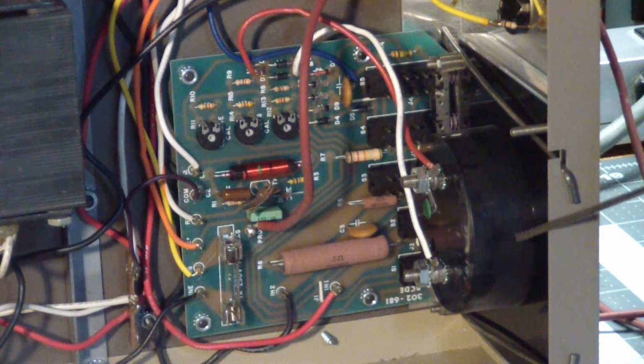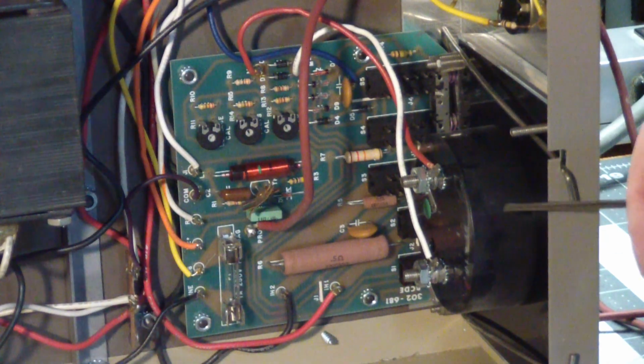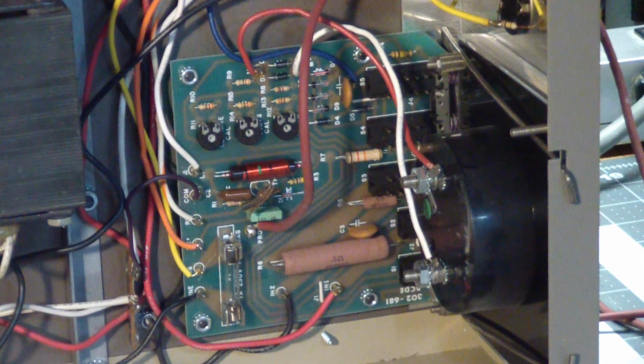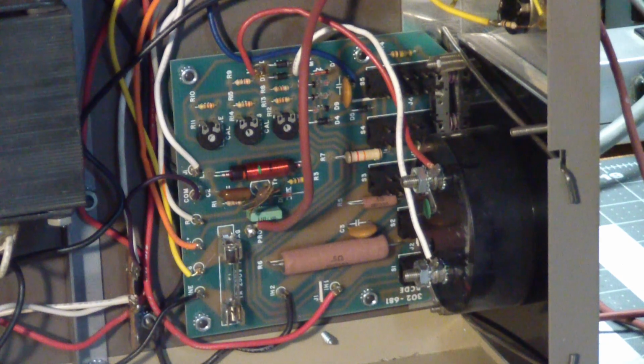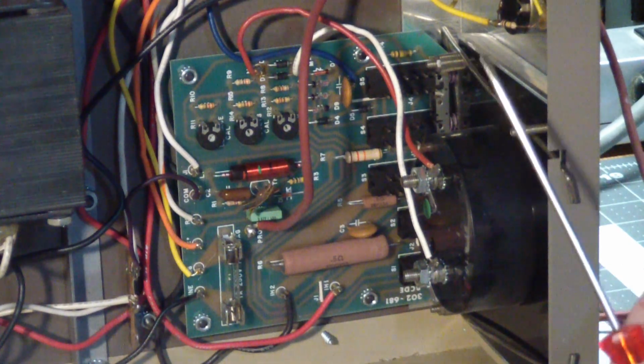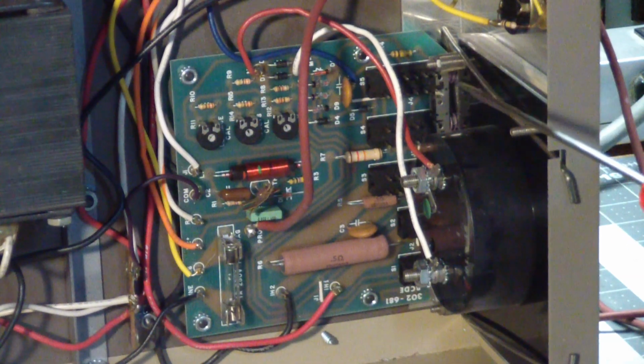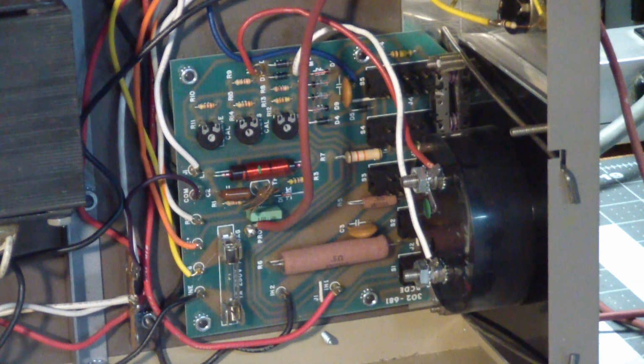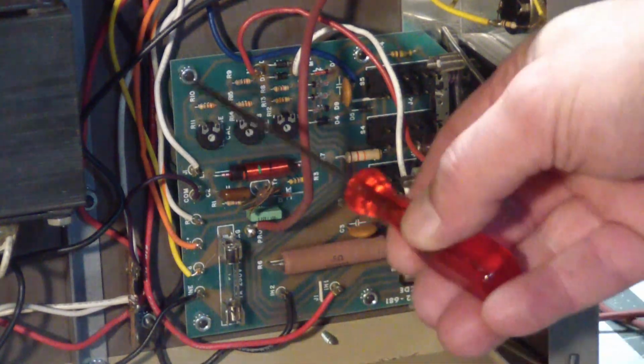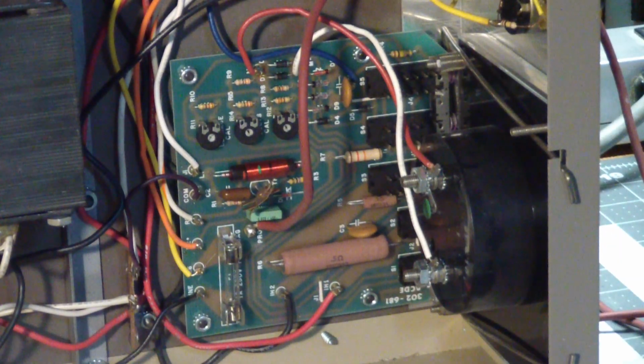To drive the meter, you need DC. So basically you tap the output coming from the auto transformer above, rectify it, shape it, and then depending on how the buttons are set in front, you drive the meter with it. Since measuring the output voltage showed a seemingly correct value, that means somewhere in here something's going wrong while translating the actual AC output to DC that can accurately drive the meter.